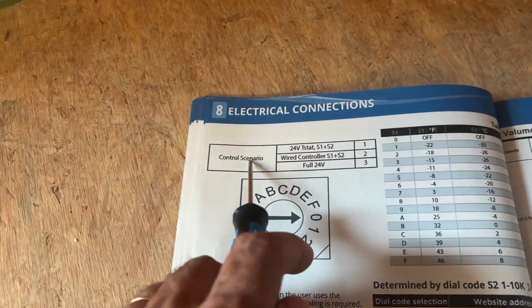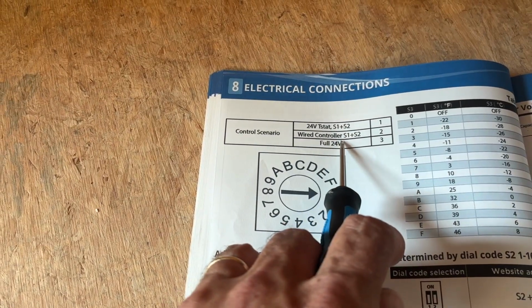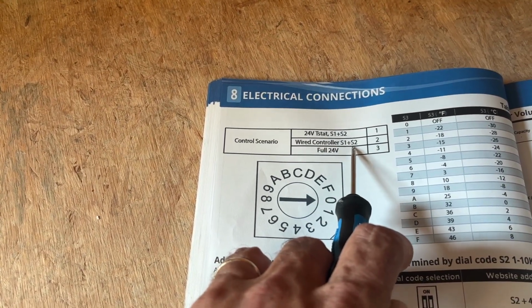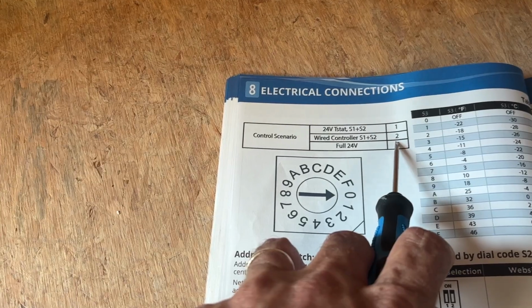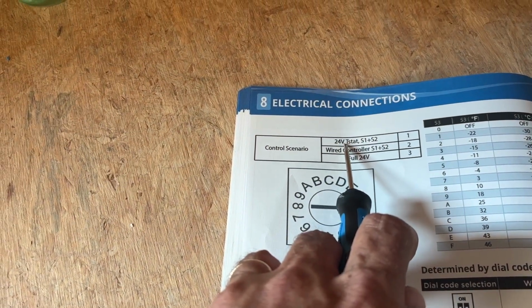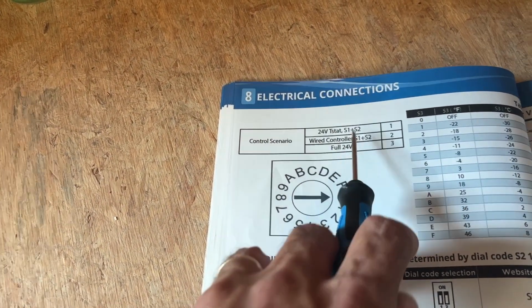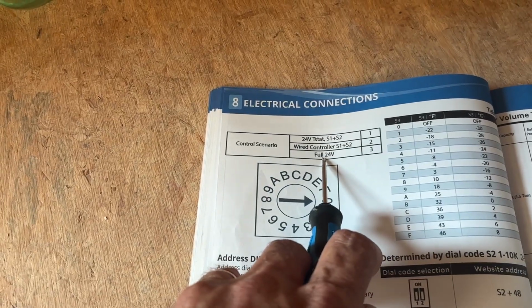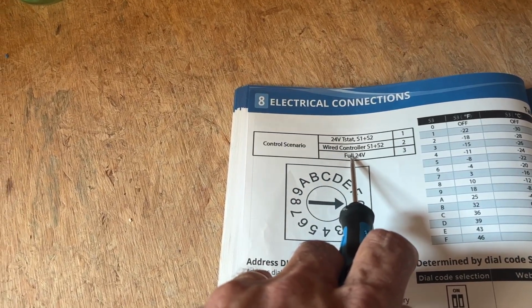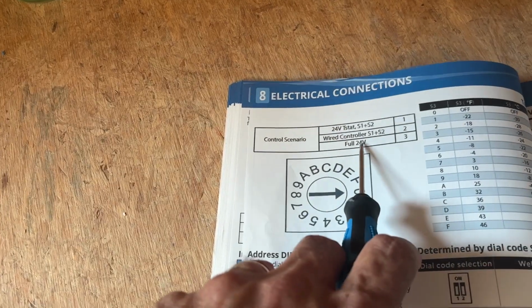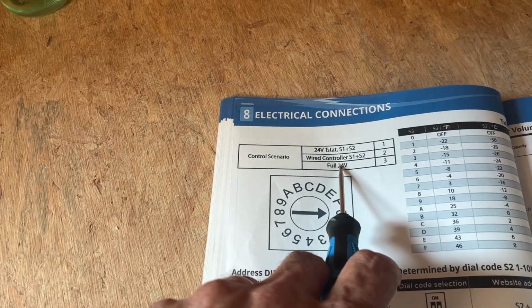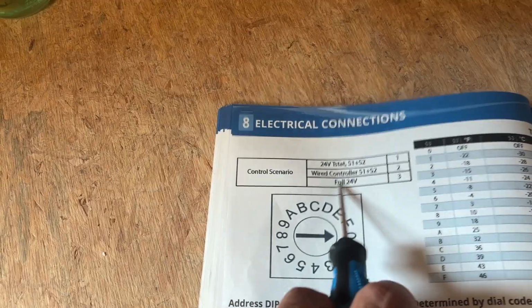Again, just going back, figure out what your control scenario is. That's if you're using the wired controller. And S1 and S2, that's control scenario 2. That's not me. I'm a 24 volt thermostat, S1 and S2. The full, my understanding with the full 24 is if you're running 24 volt power out to the outdoor unit and controlling that with thermostat wire as well.